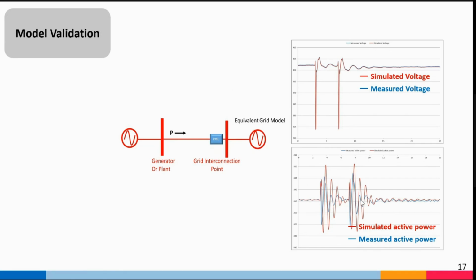During any event, the unit response should properly match with the particular event, and they use that event in the simulation software to validate whether the model provides the same response or not. So this helps in validating the model and providing feedback to the generator that your model is not proper, because with an improper model you will land up in a lot of trouble, right?